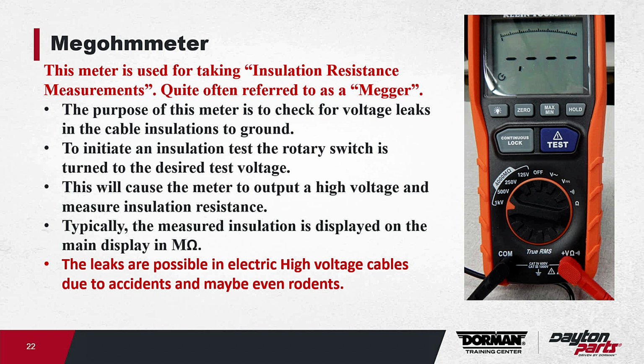To initiate an insulation test, the rotary switch is turned to the desired test voltage, and you've got a lot of choices here - I'll hold it up to see it better in a minute. This will cause the meter to output a high voltage and measure the insulation resistance. You're basically starting with low voltage and going higher and higher.